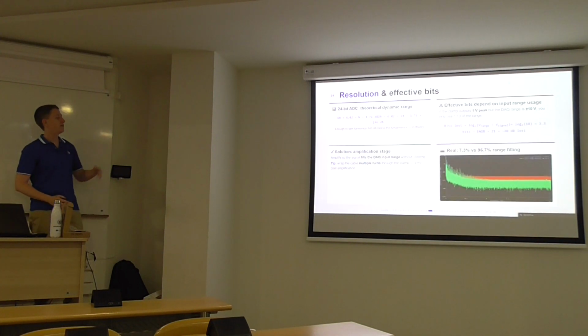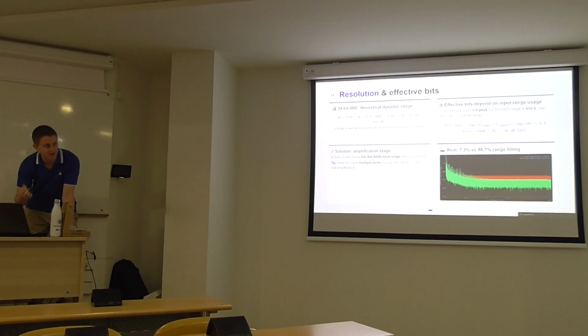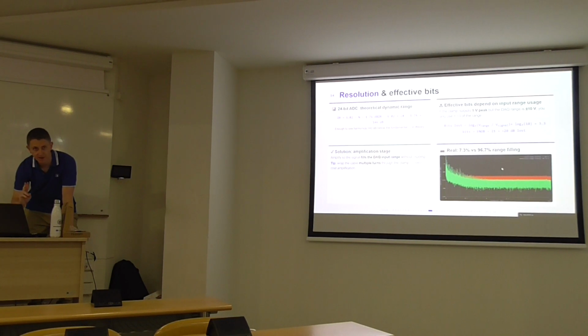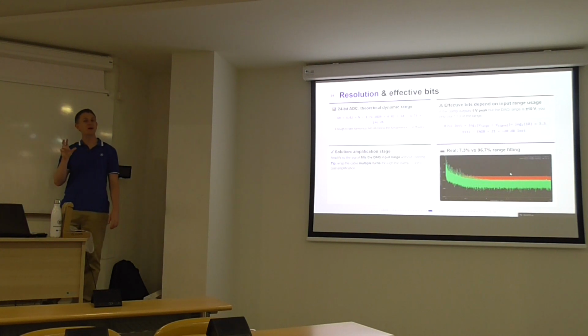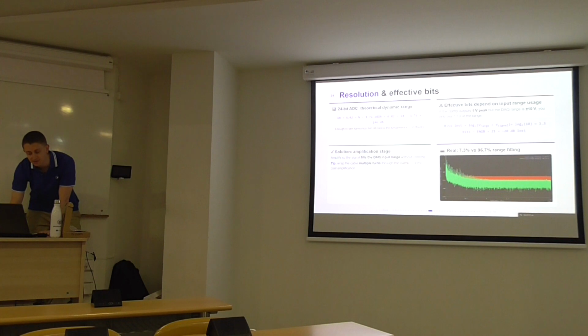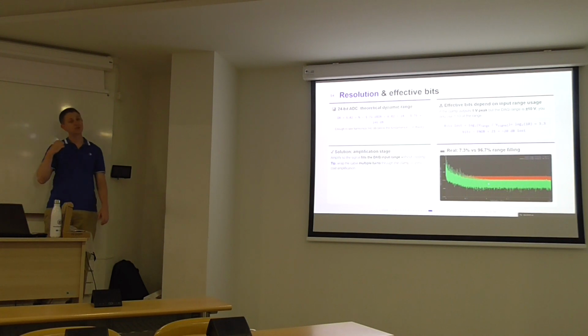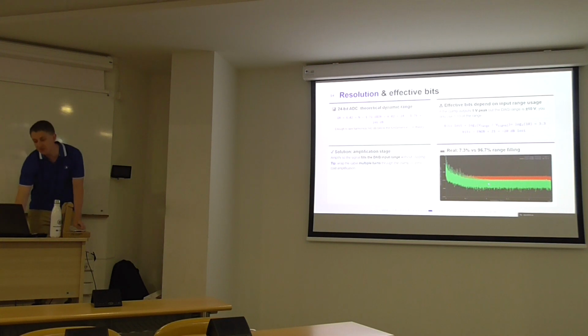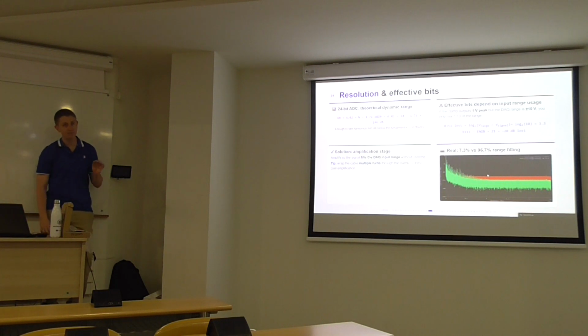Well, so here there is an example. This is a real spectrum from an induction motor fed directly from the line. Two spectrums. We have frequency on the x-axis, amplitude on the y-axis. The red one is when the input range is only filled to 7.3%, and the green one is when we fill up to 96% of the input range. As you may see here, the noise in the red one is much higher than the noise in the green one. So there are a lot of harmonics here that we can see in the green spectrum, but we cannot see in the red one. So it's super important to fill this input range so the noise is as low as possible.